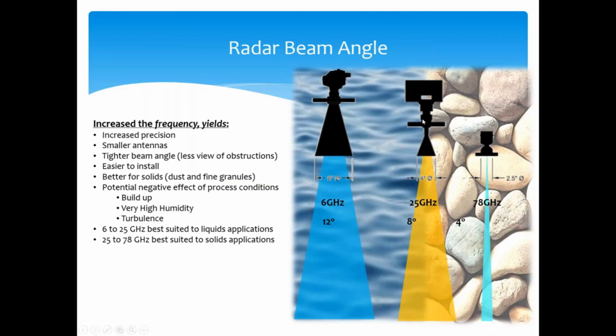We have another question asking, does the beam angle affect the distance over which it is effective? Yes and no, Eric. The only reason the beam angle would have an effect over the distance is the location of your transducer. Let's say we're up on top of a tank and we're 2 feet off of a sidewall. Well, an 8-degree beam angle might be able to make it all the 20 feet down to the bottom of your vessel before it has any obstruction from that sidewall. Whereas if we put a 12 or a 16-degree beam angle in that same vessel, we might get a reflection off the sidewall, which will cause errors, and we'll talk about that a little bit later on.